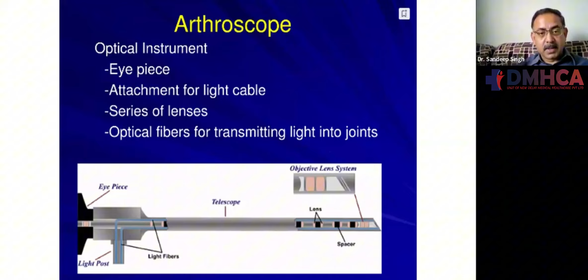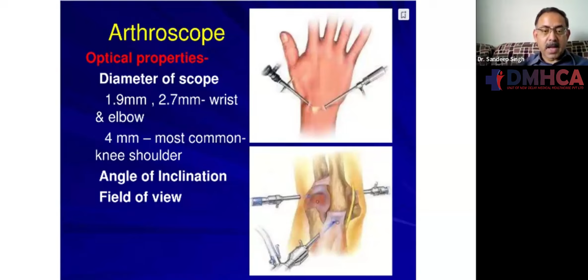So, coming to the optical properties, the arthroscope comes in various diameters, and the most commonly used diameter is 4 mm. Basically, it is used for the larger joints like the knee joint or the hip joint. Smaller probes of 1.9 and 2.7 are used for the smaller joints like the ankle, the wrist joint, or the elbow joint. Then another interesting point here is the angle of inclination. Basically, it is related to the field of view. So here you can see it can be a 30-degree scope or a 70-degree scope. It all depends on your field of vision, where it is focusing and how big your operating field is.